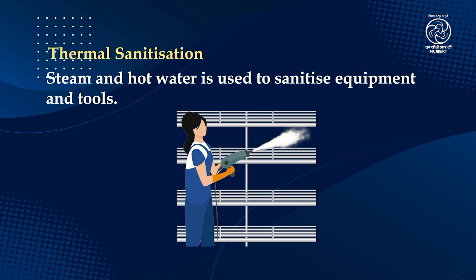In the steam type sanitization method, the steam flow in the cabinet is maintained long enough to achieve a temperature of about 77 degrees Celsius for at least 15 minutes or above. Whereas for assembled equipment, the temperature is maintained at 93 degrees Celsius for at least 5 minutes. The steam method is relatively costly as well as complex due to the difficulty in regulating and maintaining its temperature and time. The byproducts of steam condensation are also difficult to clean.